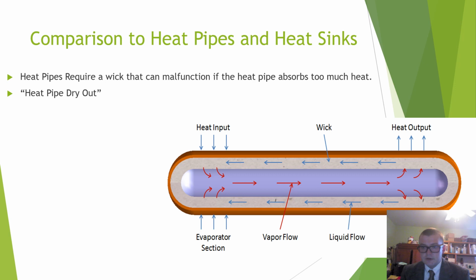Another common heat exchanger that could be used instead of a thermosyphon is a heat pipe. Comparing a heat pipe and a thermosyphon, you'll see that a heat pipe requires a wick around its inner perimeter. That wick transports the liquid, essentially doing what gravity does for the thermosyphon.